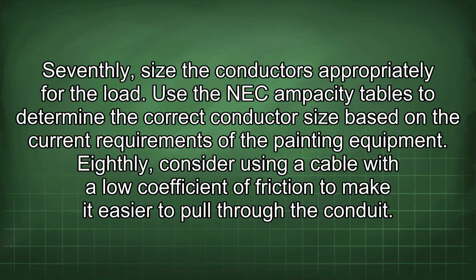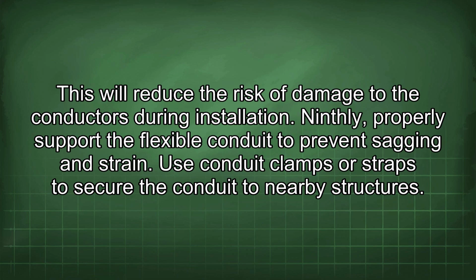Seventhly, size the conductors appropriately for the load. Use the NEC ampacity tables to determine the correct conductor size based on the current requirements of the painting equipment. Eighthly, consider using a cable with a low coefficient of friction to make it easier to pull through the conduit. This will reduce the risk of damage to the conductors during installation.